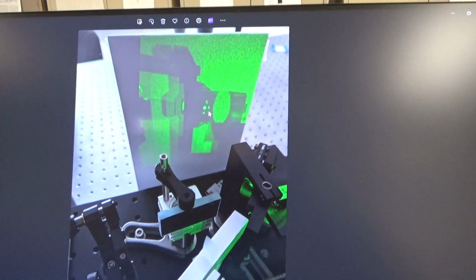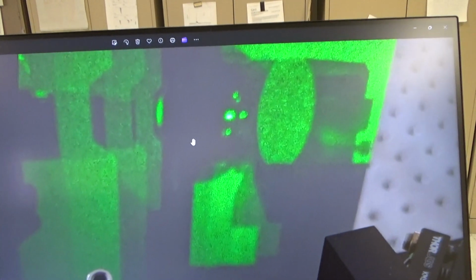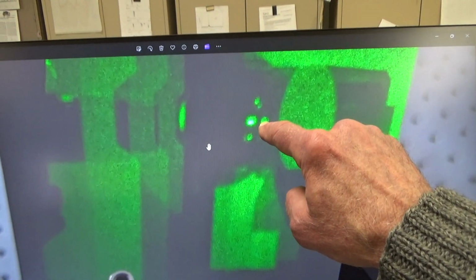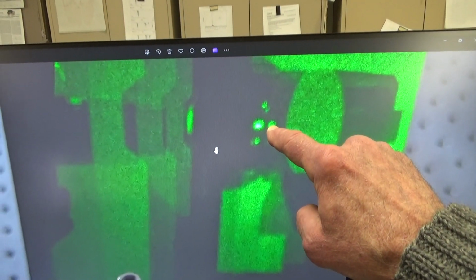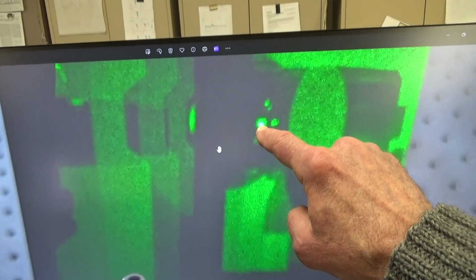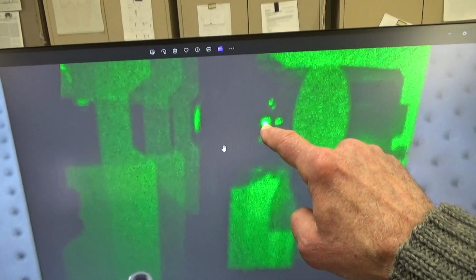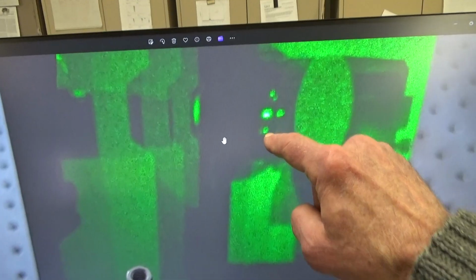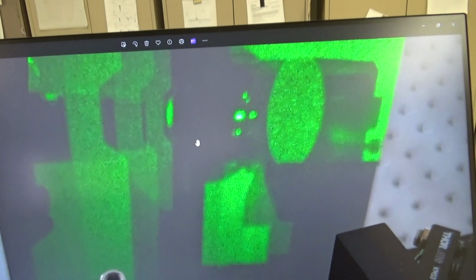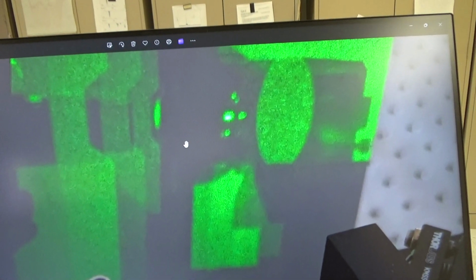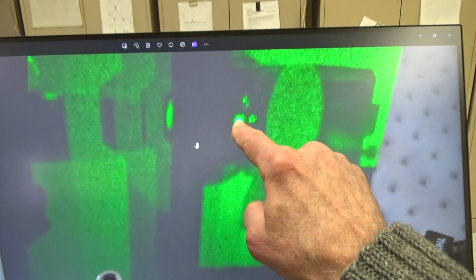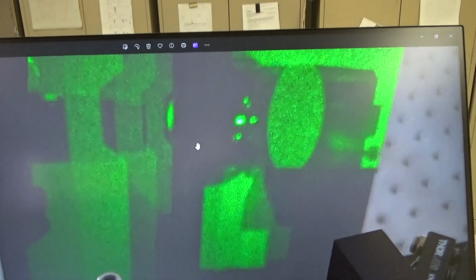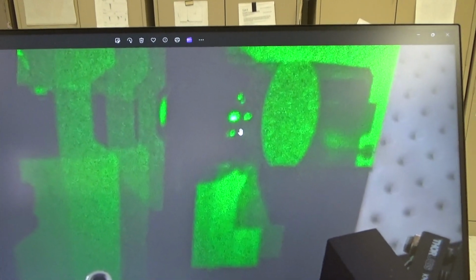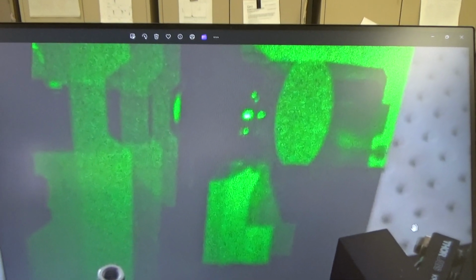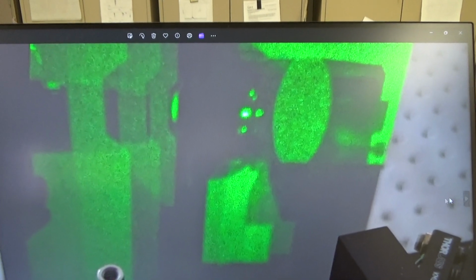What you'll see on the rear wall is two spots, one from the first pass of the green through the system, and the one that's being returned by the rear mirror. And you'll also see the extra spots from the crystal reflections as well. So you'll want to adjust the rear mirror to get the two spots to coalesce on top of each other.